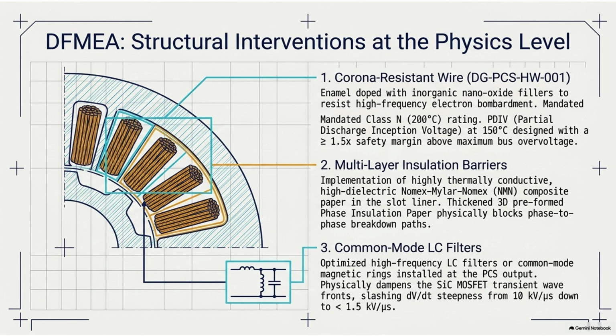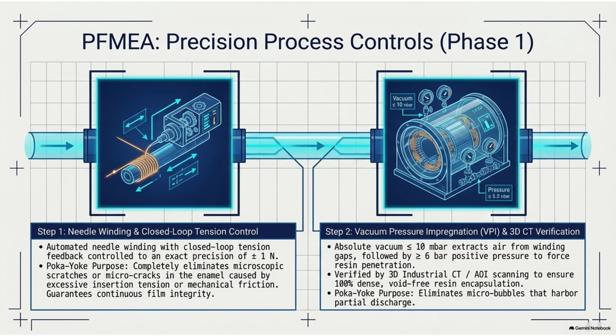Exactly. The source specifies the use of highly specialized corona-resistant wire. Corona, referring to those microscopic partial discharge sparks we talked about earlier, the ones taking microscopic bites out of the plastic. Exactly. To combat that, the wire is coated in a Class N enamel, meaning it is chemically formulated to operate continuously at 200 degrees Celsius without melting. 200 degrees, that's intense. But heat resistance isn't enough to stop the electrons. So they dope the enamel with inorganic nanoparticle fillers. Dope the enamel. So they are mixing microscopic particles into the plastic itself.